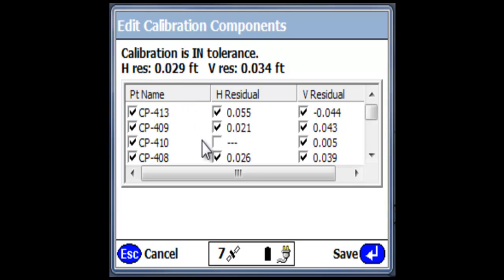What happens is my horizontal residual dropped from 32 to 29 thousandths. It's a few thousandths, and it doesn't really matter to me. It's more important to have these points included because it provides a tighter calibration. That's critical.